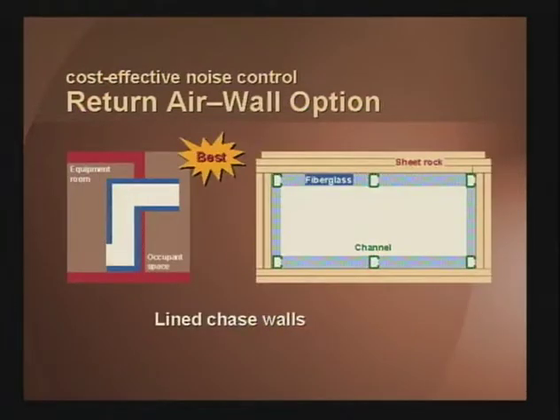The last option is the lined chase wall. Basically, this is built inside the mechanical room. You have 3 layers of 5/8 inch sheetrock on the MER side, 2 layers of sheetrock on the room side. It's an enclosed box. 2 inches of fiberglass on the inside. Sound is forced to go up through this lined chase and out over the occupied space. The lined chase wall offers you return air attenuation, plus it stiffens up the MER wall considerably, thus enhancing the wall's resistance to low frequency sound penetrating it.